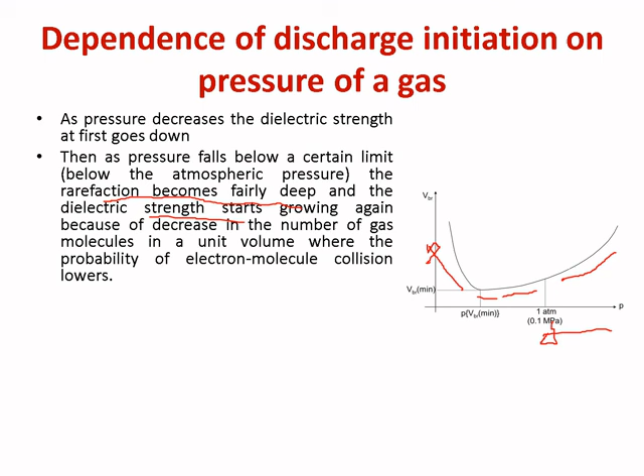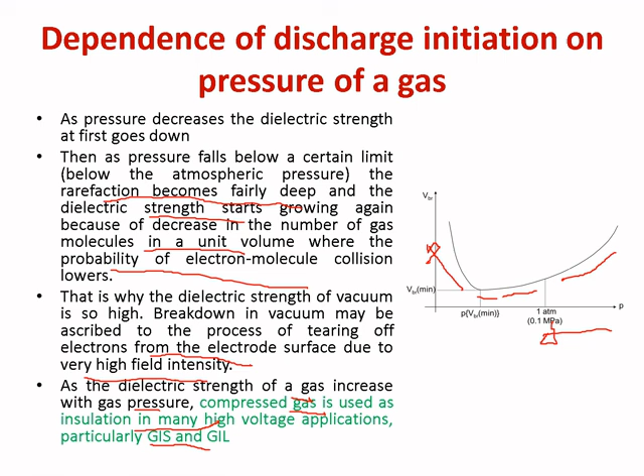Breakdown in vacuum may be ascribed to the process of tearing off electrons from the electrode surface due to very high field intensity. As the dielectric strength of the gas increases with gas pressure, compressed gas is used as an insulation in many high voltage applications, particularly GIS and GIL, gas insulated substations and gas insulated lines.